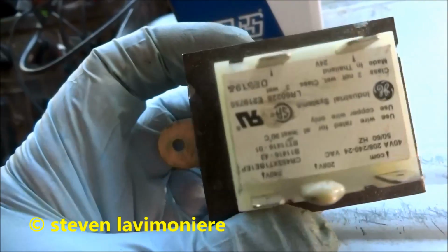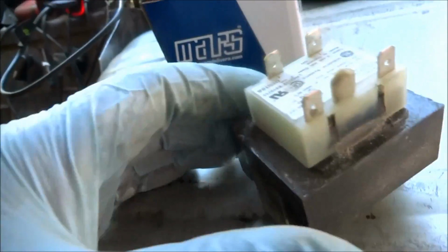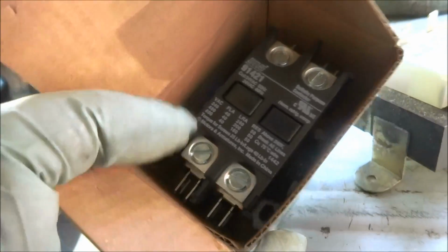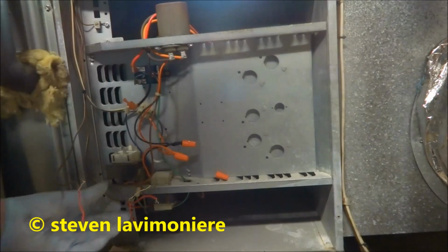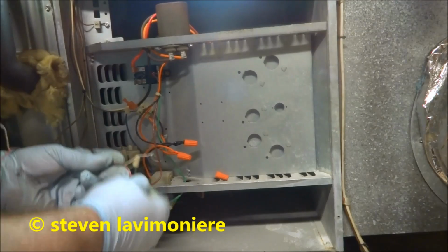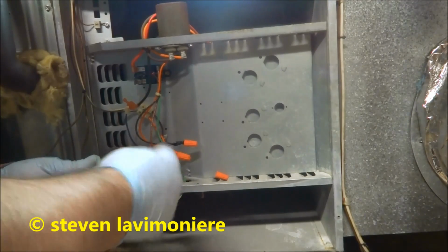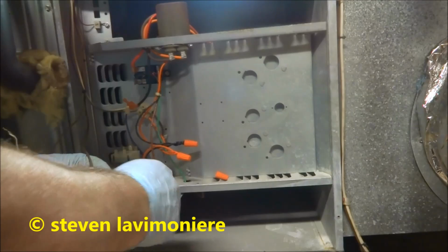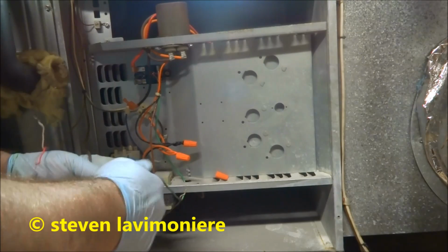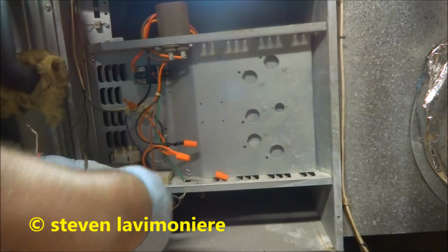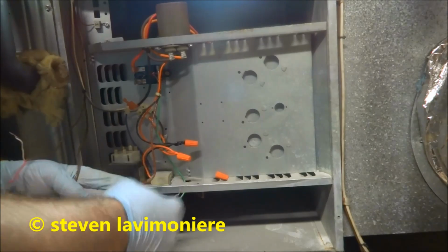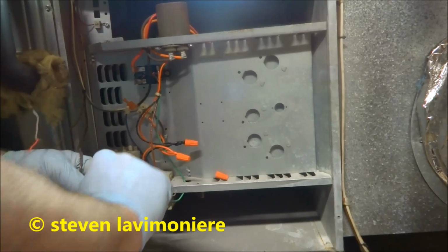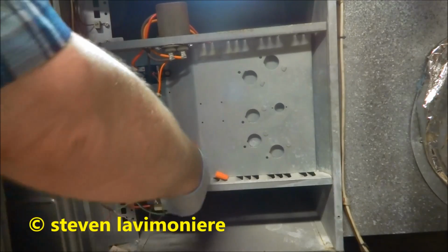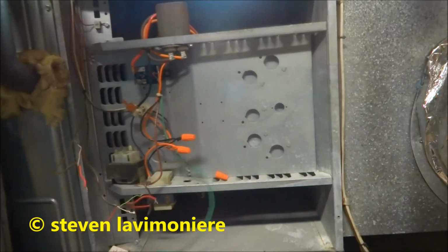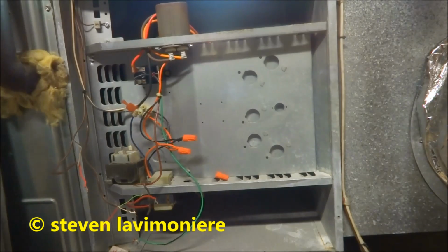Alright guys, so I got a new transformer here. And I got a new contactor for outside. The contactor's bad. The contactor fried the transformer. So we got the power going to the thermostat, the yellow coming back, and then the green for the fan. Alright. There's the green for the fan. Pull the relay in.